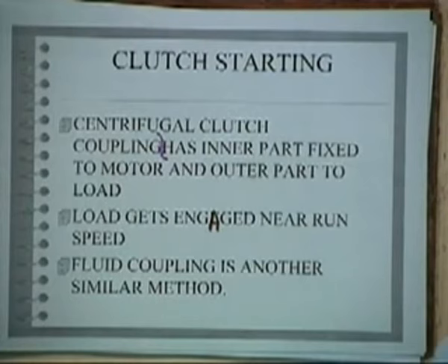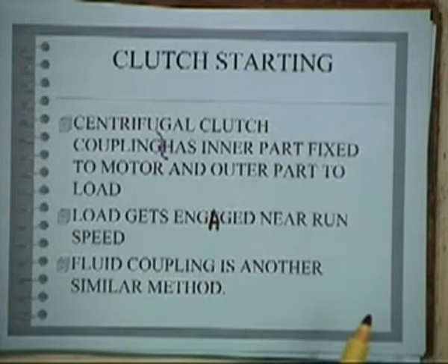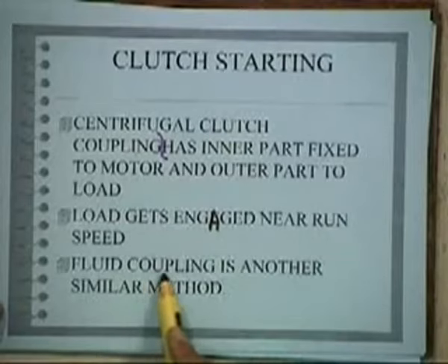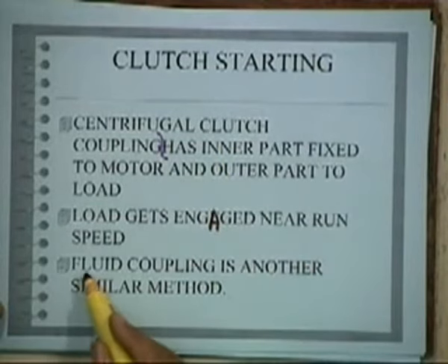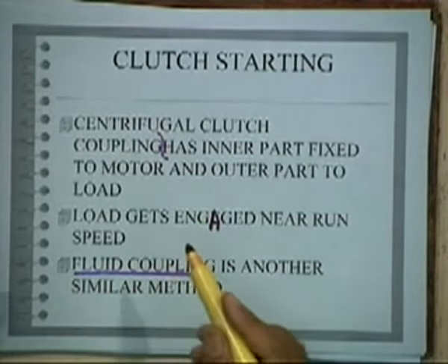The same thing is in fact being used in many thermal power plants for large motor starts. If you have a large motor to start, it is preferable to start it with no load and run it with full load. Therefore, apart from the clutch, one of the methods is called a fluid coupling. The fluid coupling has the same feature as a clutch.